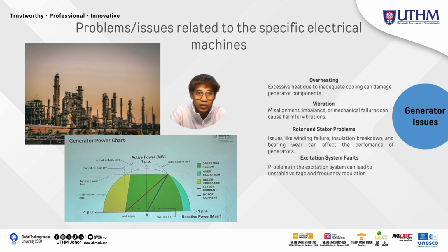For the problems or issues related to the specific electrical machines, we have generator issues. The first is overheating, as excessive heat due to inadequate cooling can damage generator components. And second is vibration; misalignment, imbalance, or mechanical failures can cause harmful vibration. And the third is rotor and stator problems. Issues like winding failure, insulation breakdown, and bearing wear can affect the performance of the generator.